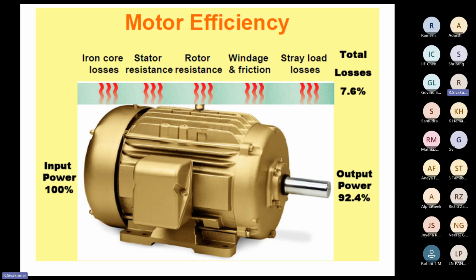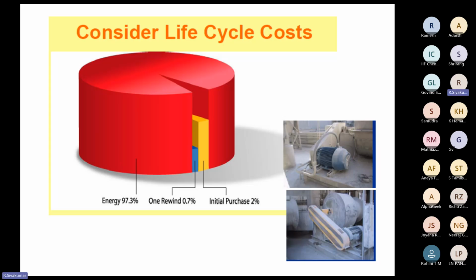These are the various losses associated with motor efficiency: iron loss, core loss, stator loss, rotor resistance, windage, stray loss. So almost 7.6% to 10% losses will happen, and only somewhere around 89 to 90% will be given as output. During the procurement of a motor, we have to consider this, because in this whole pie chart, if the motor is running for 10 years, the energy cost itself is nearly 97.3%, above 95%. Purchasing cost is only 3 to 4%, and other maintenance cost is 1 or 2%.